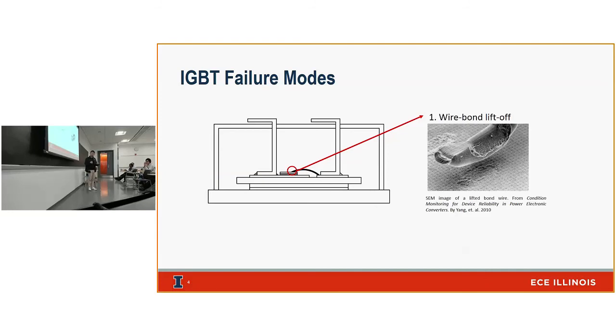There are typically a few different failure modes. One is bond wire liftoff: the bond wire is made of some conductor and bonded to the silicon chip. Because these are two different materials, once they undergo thermal cycling, they expand different amounts, causing thermal mechanical stress. On the right, you can see a scanning electron microscope image of what a lifted bond wire might look like.